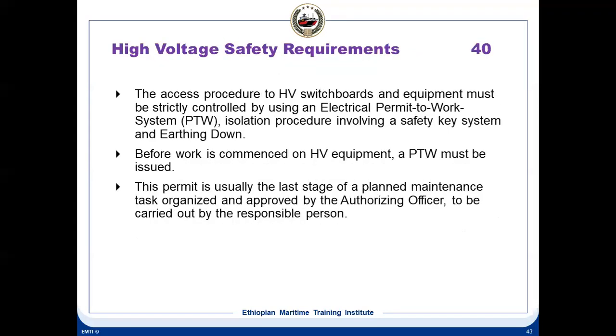The access procedure to high voltage switchboards and equipment must be strictly controlled. That is why high voltage switchboards are restricted on board ship. Only authorized people are allowed to enter the high voltage area, not like a normal 440 switchboard where anybody can enter. It is not allowed, by using an electrical permit to work system, PTW, and an isolation procedure involving a safety key system and earthing down. All high voltage switchboard panels have safety keys. If you want to open a breaker cover, front side or back side or anywhere, there are keys for this, safety keys. So the keys have a security safety system. That procedure has to be followed when opening these panel covers. And earthing down is the first thing. First is earthing down, then the safety key system. These are the two important factors in this.